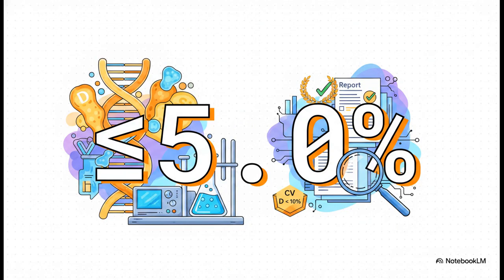So the crucial point here is this number, less than or equal to 5.0%. To even meet that CDC VDSCP certification, laboratories have to hit this exact mean bias target against reference methods, alongside having an imprecision coefficient of variation of less than 10%. When you're writing up your methodology, directly quoting these exact targets is a surefire way to prove to reviewers that your lab data is airtight.